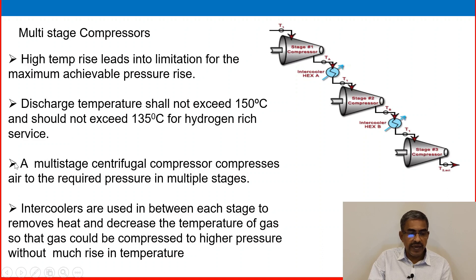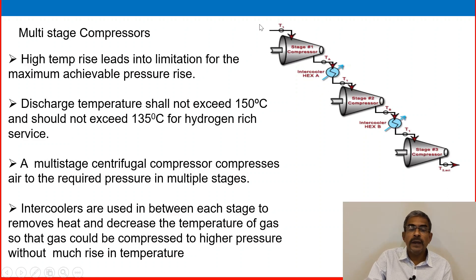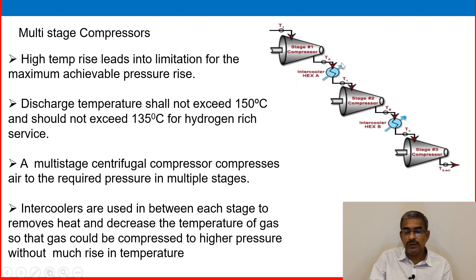Discharge temperature shall not exceed 150°C and should not exceed 135°C for hydrogen-rich services. A multi-stage centrifugal compressor compresses gas to the required pressure in multiple stages. Intercoolers are used between each stage to remove heat and decrease the temperature of the gas so that the gas can be compressed to higher pressure without much rise in temperature. When pressure increases in stage 1, temperature also increases, so we cool the gas between stages using an intercooler to bring temperature down before compressing again in stage 2.